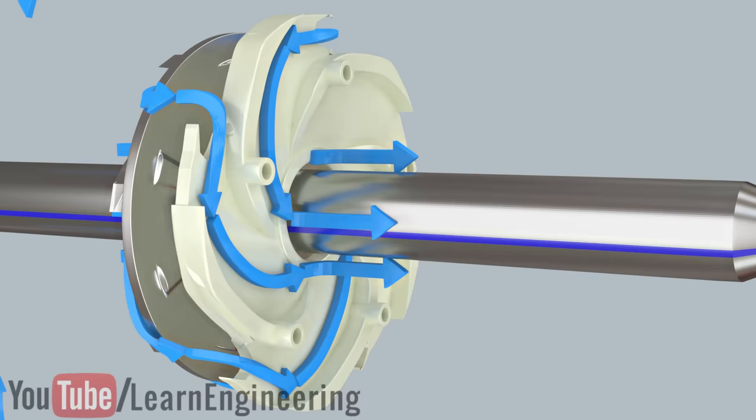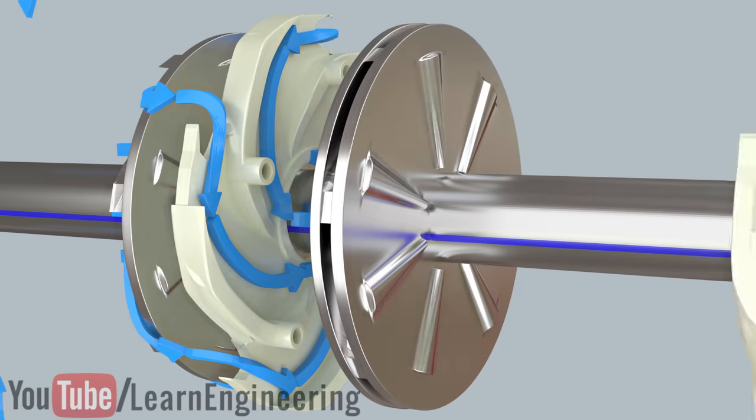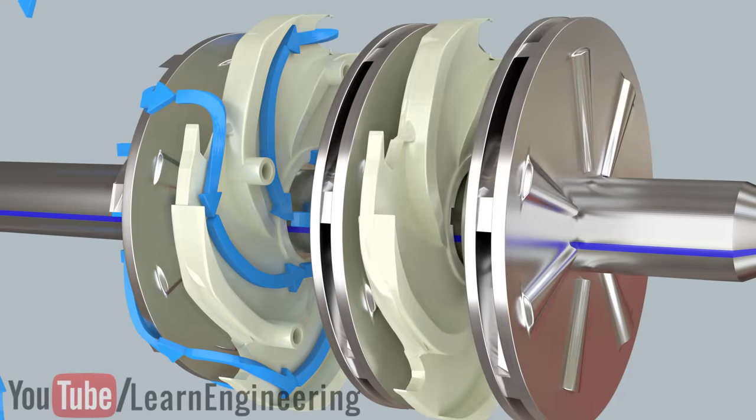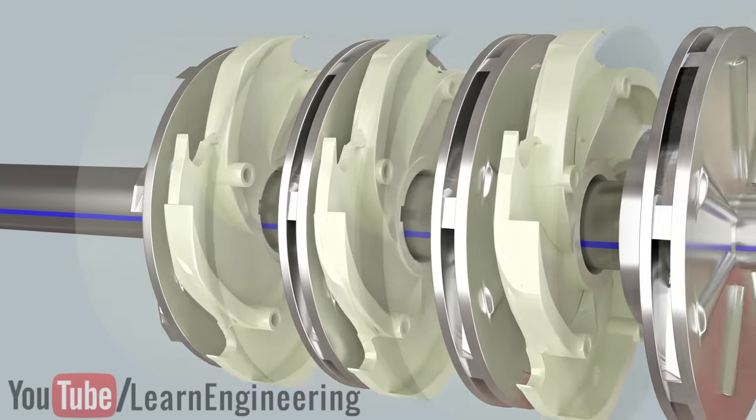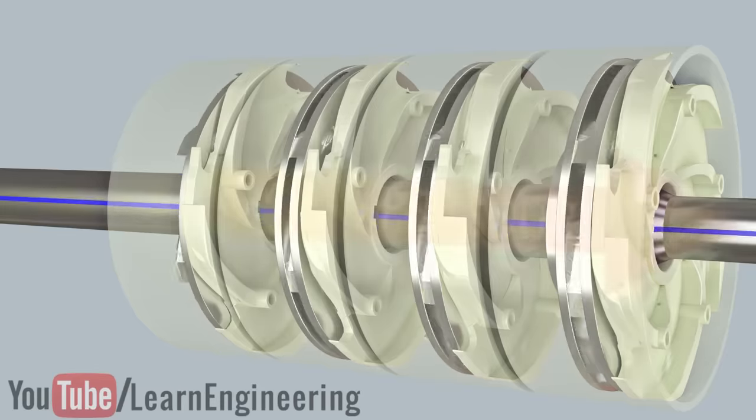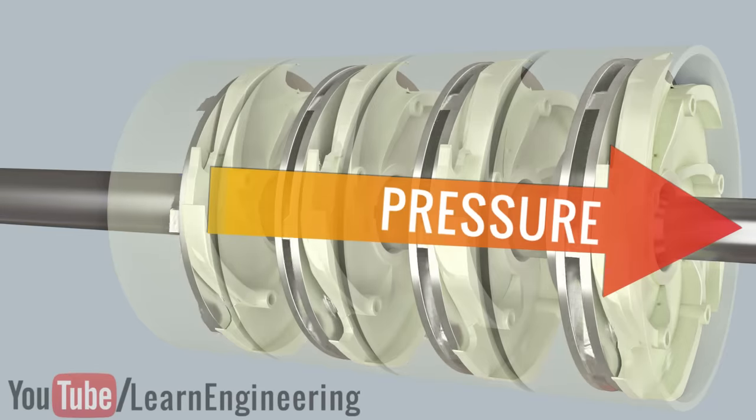The next impeller is connected to the outlet of this diffuser. The series of connected impellers multiplies the pressure gain at each stage. This is the reason why submersible pumps produce a huge amount of pressure head.